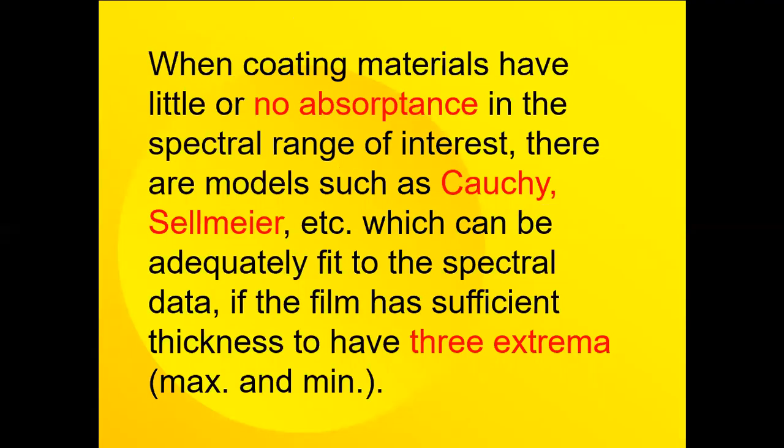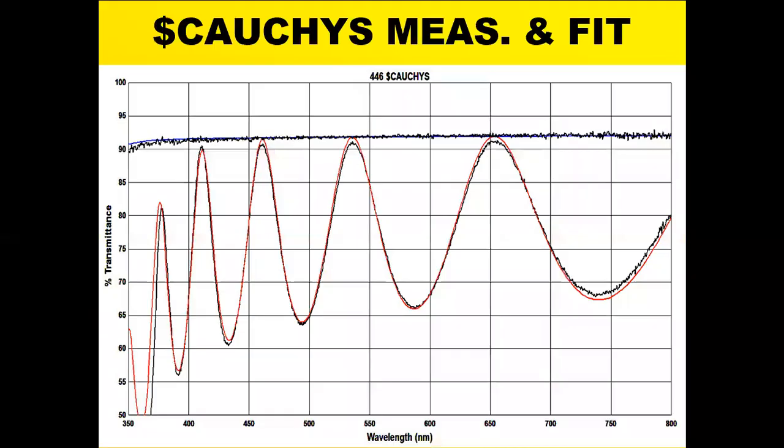When coating materials have little or no absorbance in the spectral range of interest, there are models such as Cauchy and Sellmeier which can be adequately fit to the spectral data if the film has sufficient thickness to have at least three extrema in the spectral range. This one, of course, has over half a dozen extrema.